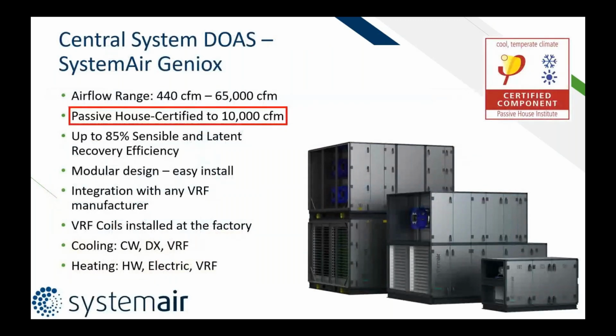So moving on from the in-unit ERVs, we're going to talk about central systems now. Now, this is an amazing unit. We're very lucky, very excited to have it. This SystemAir Geniox unit has a huge airflow range, up to actually 65,000 CFM, realistically closer to about 50,000 CFM once you apply static pressure. But the Passive House certified range is up to 10,000 CFM, including static pressure.